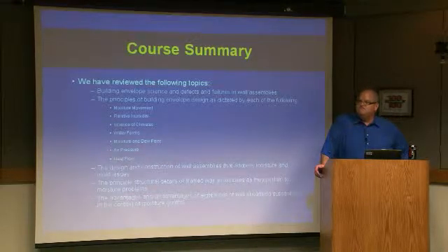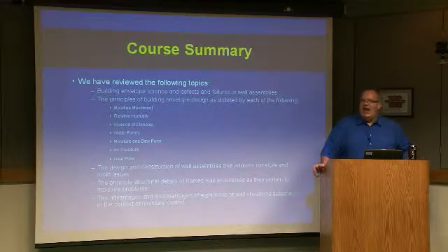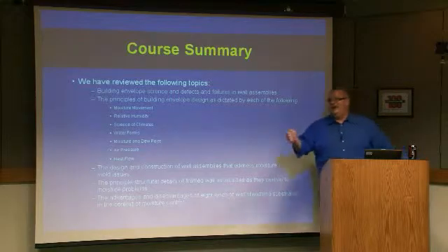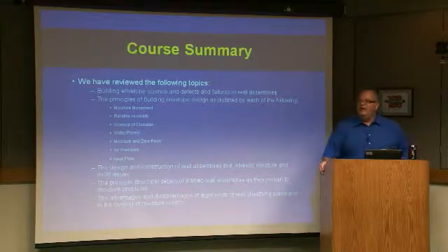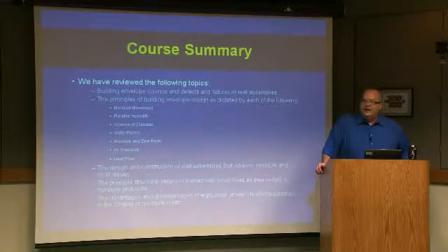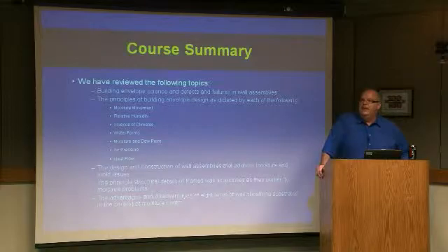And is that kind of what you were referring to when you were saying there's relative and there's absolute? Yeah. Absolute is that chart of inches of mercury. That's a measurement. It's got nothing to do with temperature changes. That actually tells you what the mass of water is. Now you know how much water is present. Now you know what temperatures you can live with. So that's absolute humidities, and that's where all the simulations on calculators are done, in absolutes.